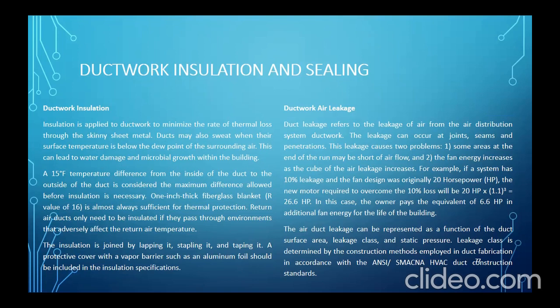So may dito na kaya. 1-inch thick fiberglass blanket, R value of 16, is almost always sufficient for thermal protection. So return air ducts only need to be insulated if they pass through environments that adversely affect the return air temperature. So normally yung supply lang. So sa return, check yung temperature na kung more than 15, so kailangan mo ng insulation.